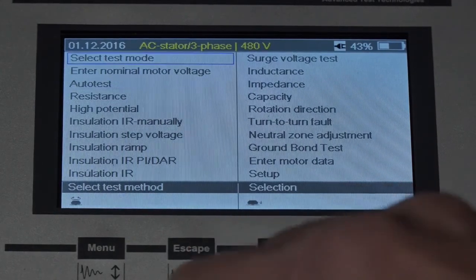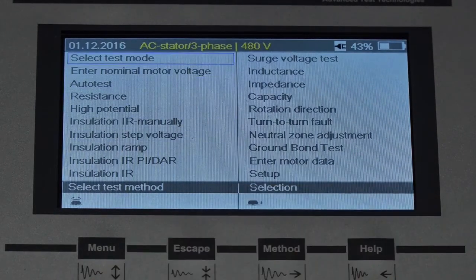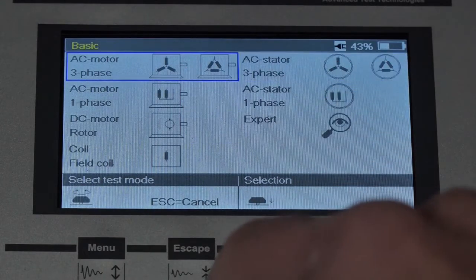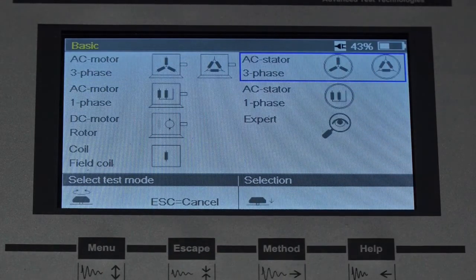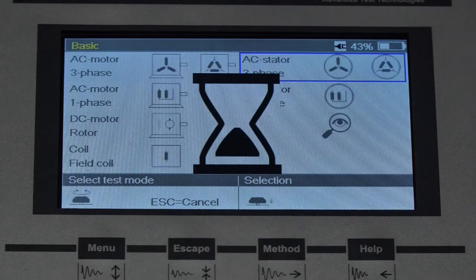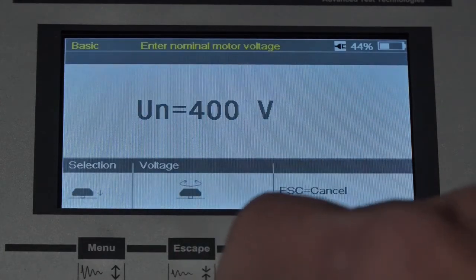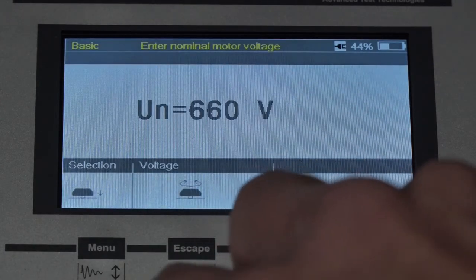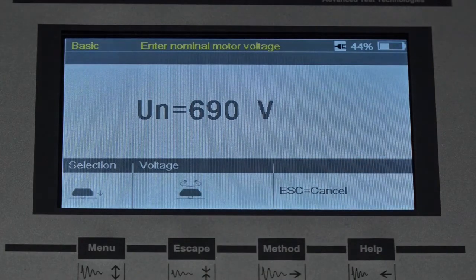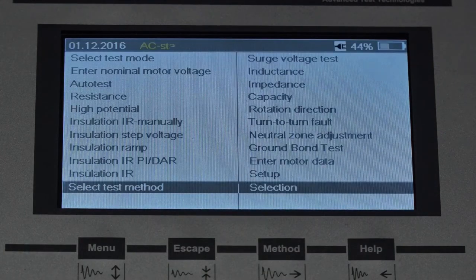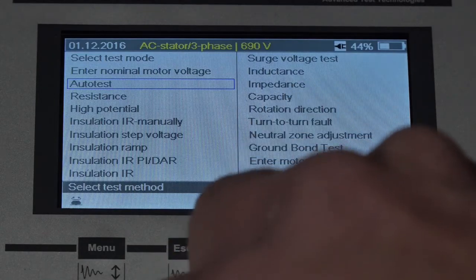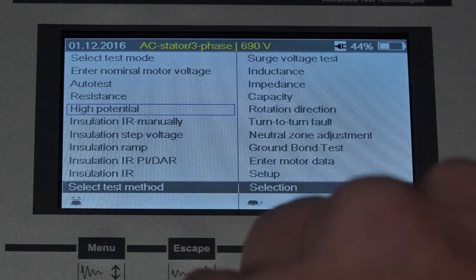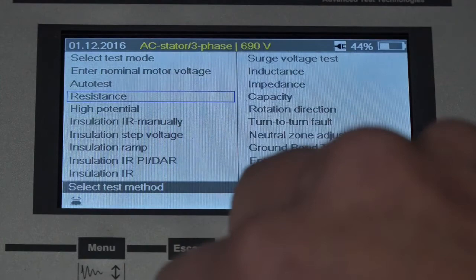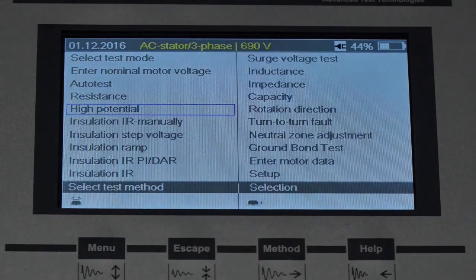So let's select a test mode of just testing a stator, which you can see there on the upper right side of the screen. We'll select that. It will ask us what voltage we want to test, or what the motor voltage is. Let's max it out at 690, and we'll select that. Now that 690 has automatically selected specific test voltages for doing the high voltage DC test, or a high pot test. So let's use the whiz wheel to select the high potential item.